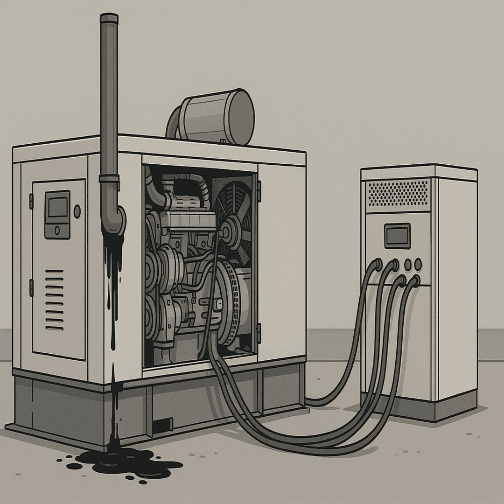Makes sense. And then there are environmental things like running the engine constantly in very cold weather without letting it warm up properly. Prolonged idling is a classic contributor too. Just letting it sit there, running with no load. Terrible for it, really. Yeah. And even infrequent use can be a factor. If a generator sits for long periods, moisture can build up inside, which doesn't help things when it does run. Okay, so a whole collection of potential causes. But low load is king. Now we know what it is and why it happens.